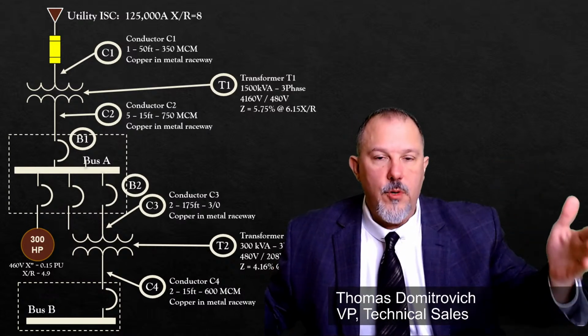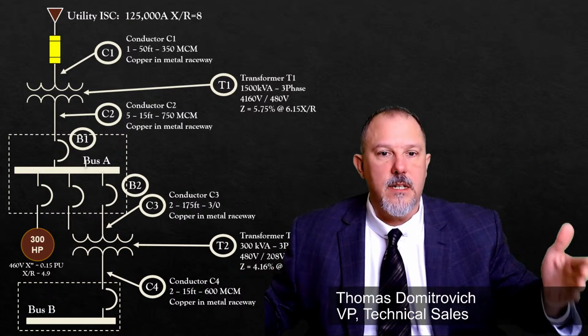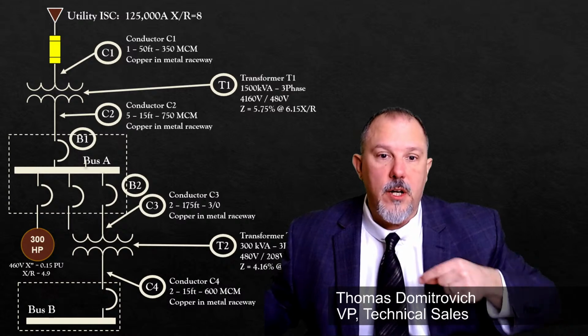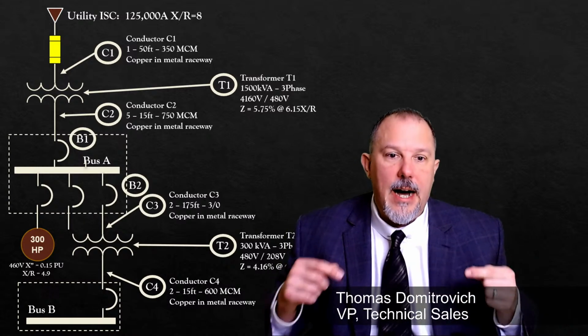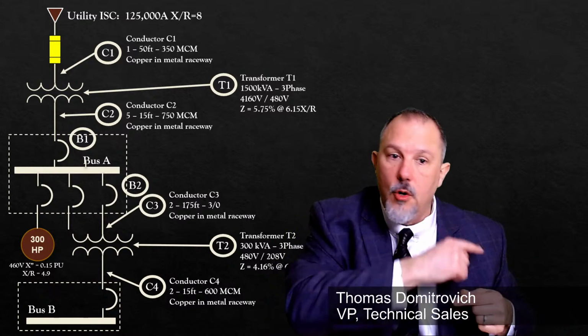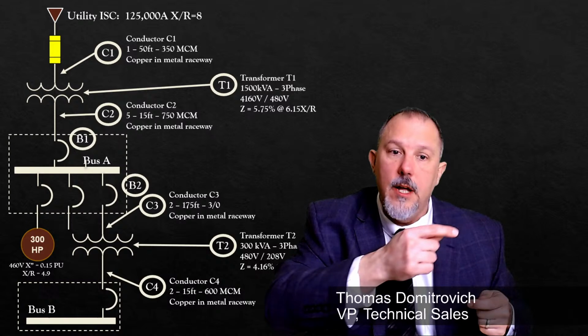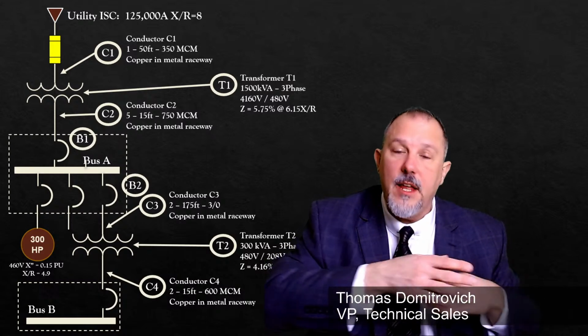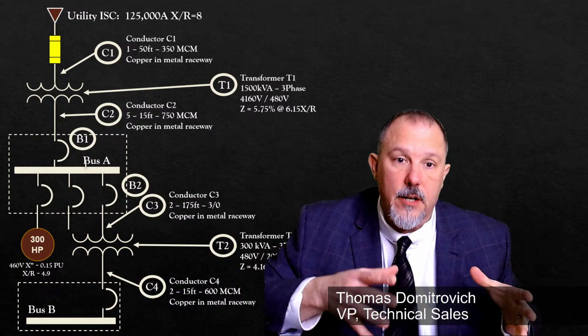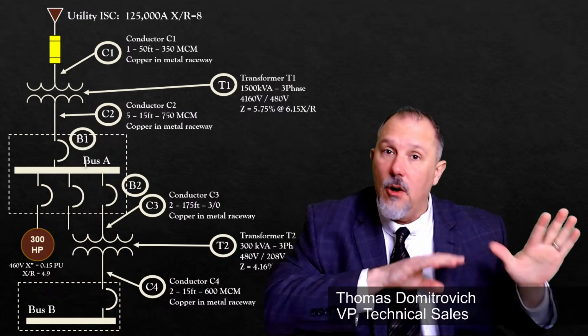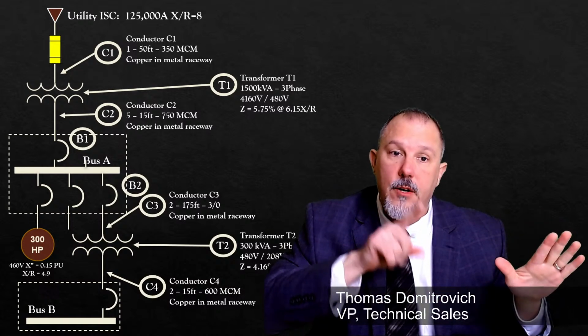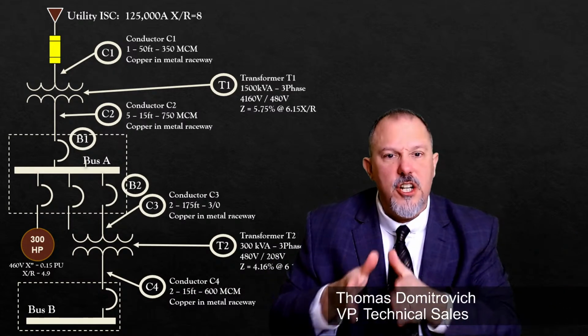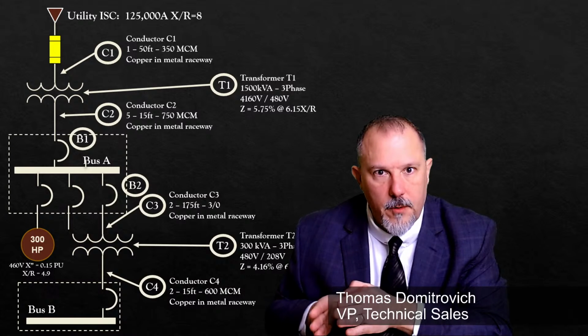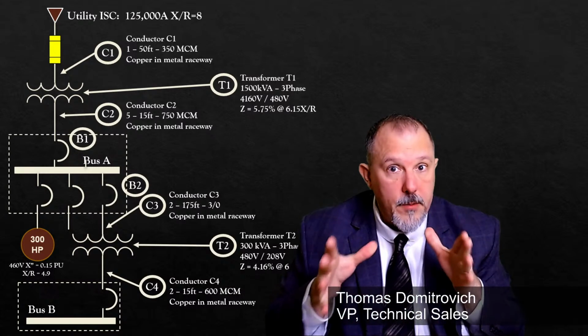Breaker 1, which is the main in this switchboard, has to selectively coordinate with breaker 2, because if they don't, I'm going to lose those other loads. That motor's not going to be supplied with power, and any of the other feeder or branch circuits in this switchboard all lose power too if breaker 1, the main, goes out, and not just breaker 2, which feeds that transformer. So that's the whole purpose of selective coordination.